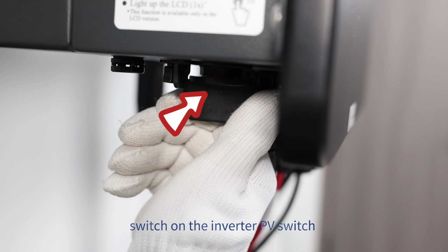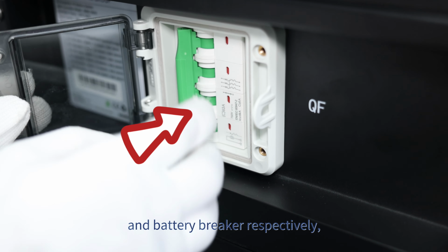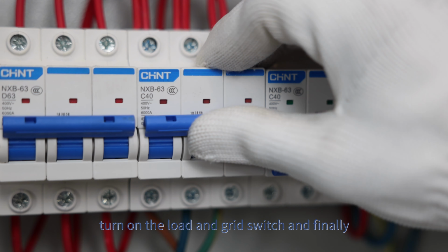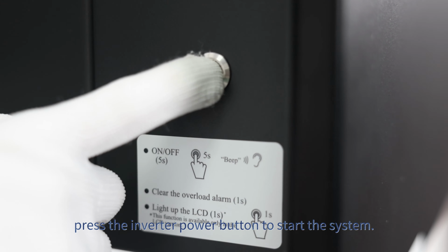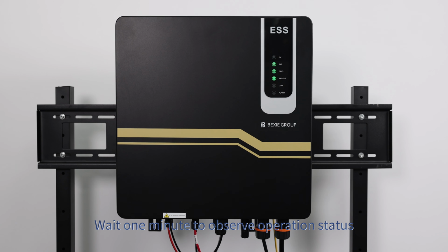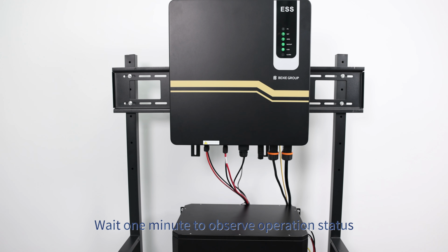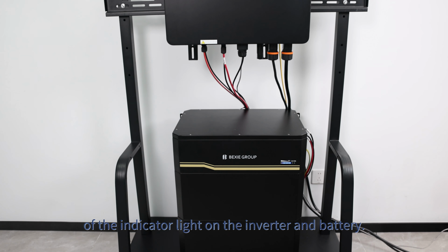Switch on the inverter PV switch and battery breaker respectively. Long press the power button, turn on the load and grid switch, and finally press the inverter power button to start the system. Wait 1 minute to observe operation status of the indicator light on the inverter and battery.